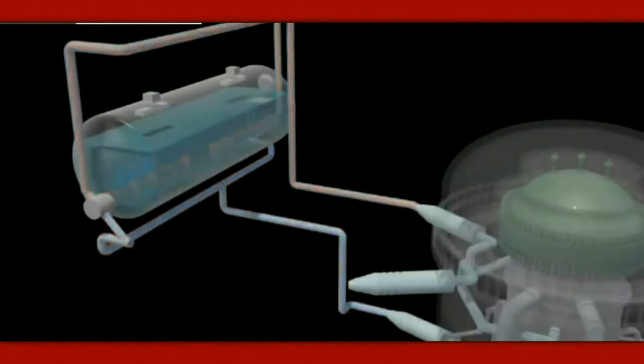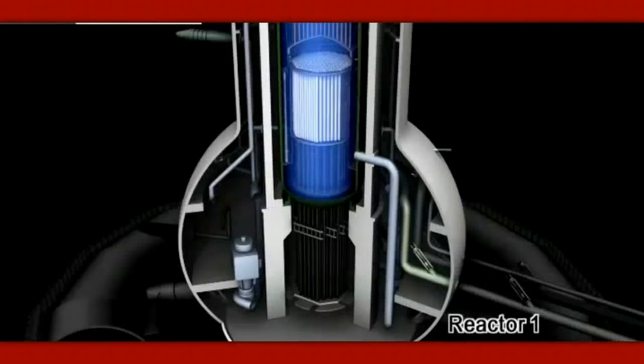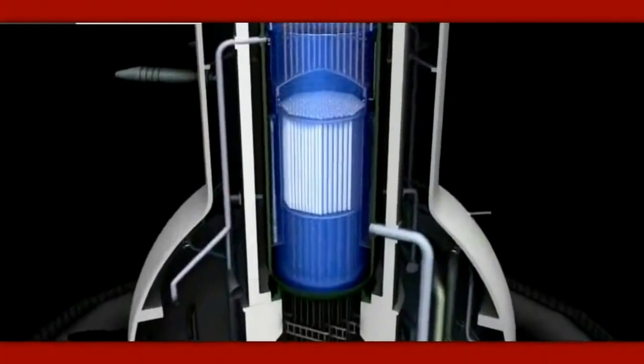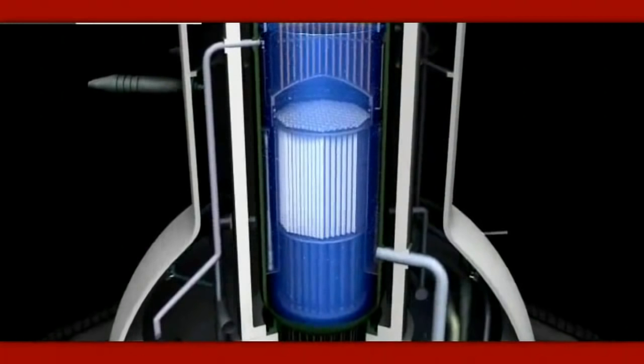But workers had been operating the machinery at intervals. The system happened to be idle when all power was lost. From that point on, the reactor quickly headed into meltdown. When the tsunami hit, water filled the reactor to a depth of 4.4 meters above the nuclear fuel rods, or top of active fuel. The water level rapidly began to fall.